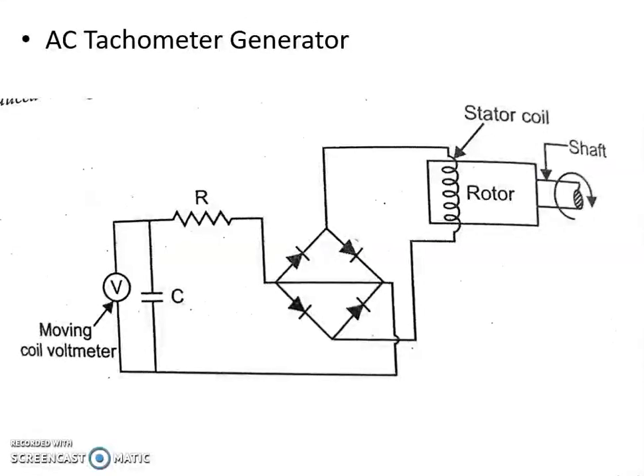Now let us discuss the AC tachometer generator. This AC tachometer generator overcomes the problems associated with the DC tachometer generator due to the presence of commutator and brushes. It consists of a stator coil and a rotor, and its construction is like an alternator — it has a stationary armature (stator) and a rotating field system (rotor). The shaft whose angular velocity is to be measured is connected to the rotor. As the rotor rotates, EMF is induced in the stator coil.